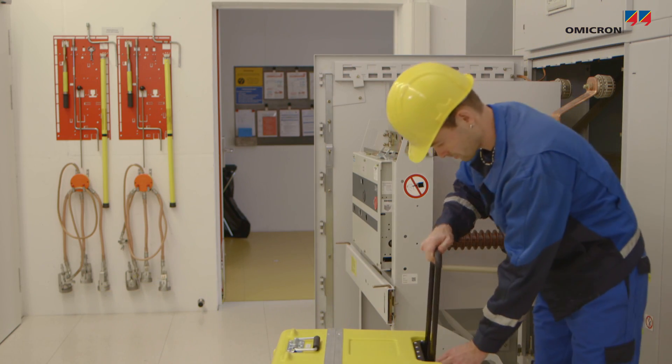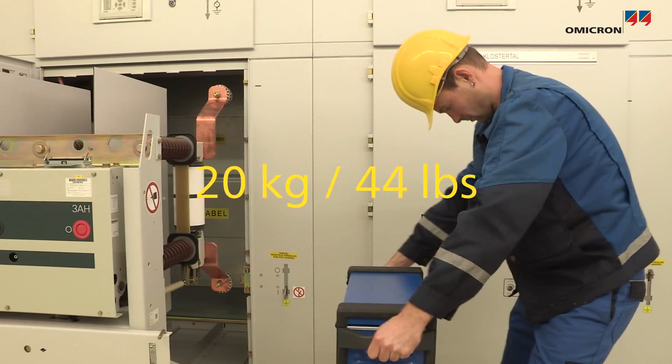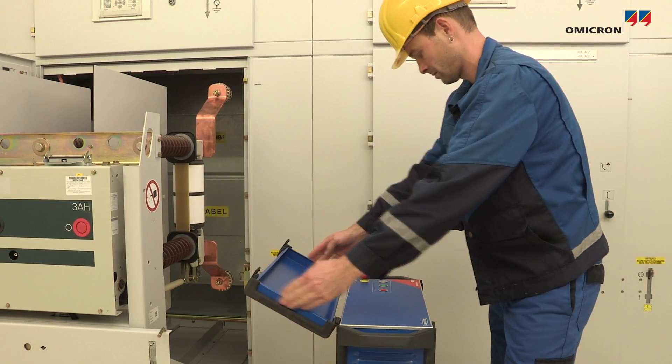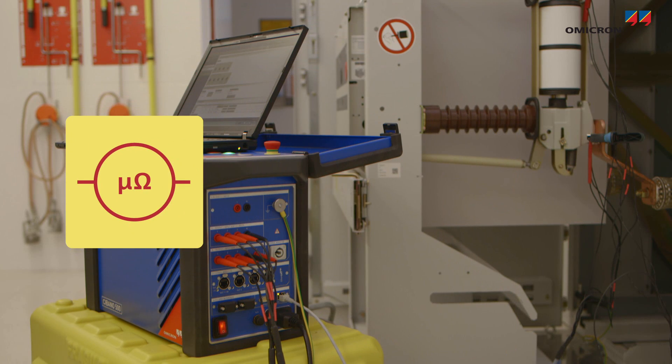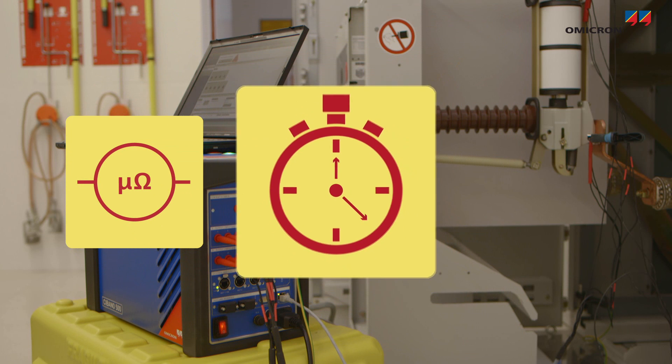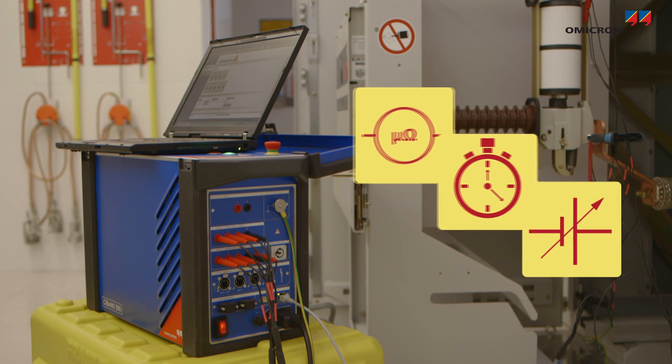The same approach has been followed with Omicron CIBANO 500, which combines all of the equipment that's needed for circuit breaker testing in one device. A micro ohm meter, a multi-channel timing unit, a controllable DC supply to power drive motors and trip and close coils.